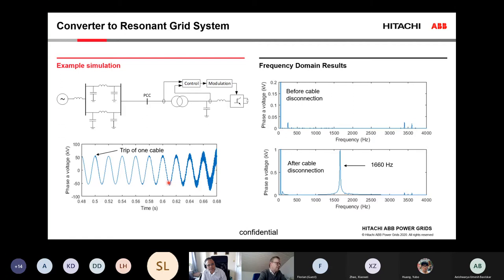To see what that actually is, it's useful to look at the Fourier transform of this voltage. In the upper picture, we have the Fourier transformed voltage taken in the time period before the disturbance. We can see we have some fifth harmonic, a little bit of seventh harmonic, and around the switching frequency we have harmonics. But after the cable disconnection, where I've taken the Fourier transform of the voltage in this region, we see a different picture. We still have the switching harmonics, but on top of that, there is a huge harmonic distortion at about 1.7 kilohertz. And this is because something in the control system has gone unstable when the grid changed.